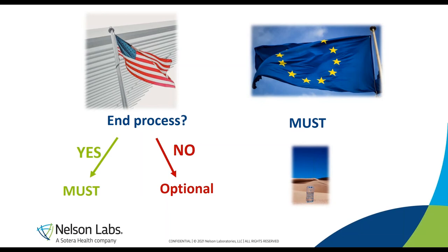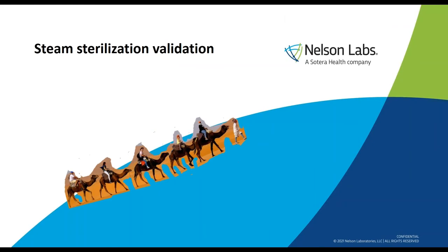When must you perform a thermal disinfection validation? For Europe, if you describe a thermal disinfection process in your instructions for use, it is a must to validate it using the A₀ approach. For the US market, if it's a final process step you must validate it; if it's intermediate prior to sterilization, validation is optional. If applying for both markets, you must validate using the A₀ method for Europe.